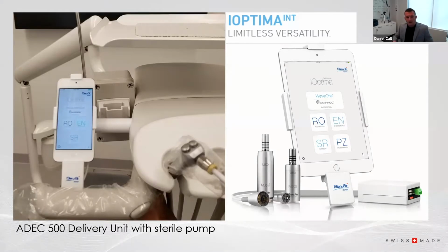The first one is the restorative electric handpiece system. That is our Vanguard product, which has the capacity to control a sterile pump. This will retrofit onto any dental unit in the field and immediately give you a pump installed on the delivery unit. With that pump, you can then run a sterile irrigation pouch with a sterile irrigation line, disposable between patients. And our system can actually control a surgery motor with a surgery cable that can be disconnected and sterilized. So there are options out there to bring your dental unit as current as possible to infection control standards without having to buy an entirely new dental unit.